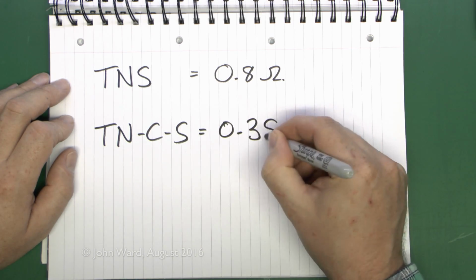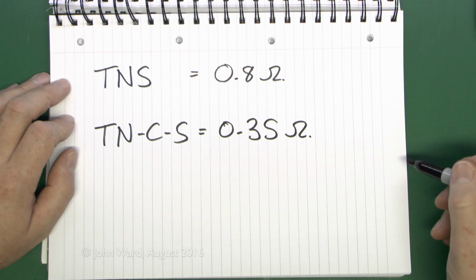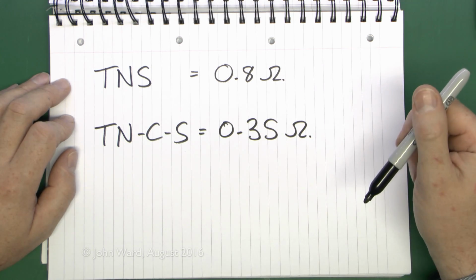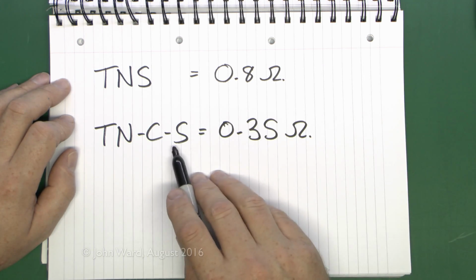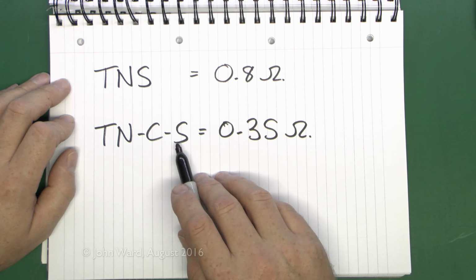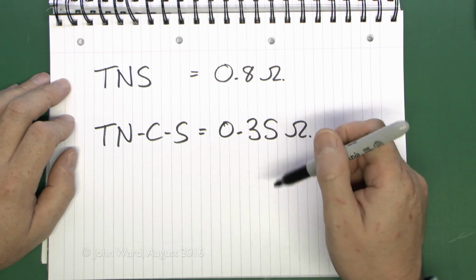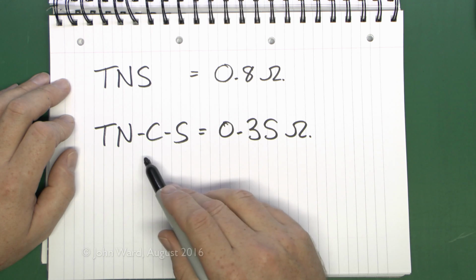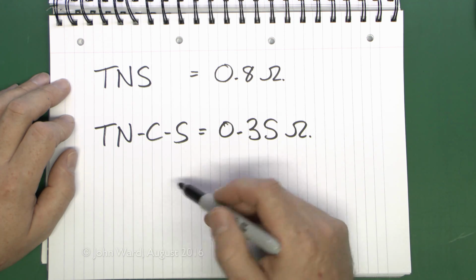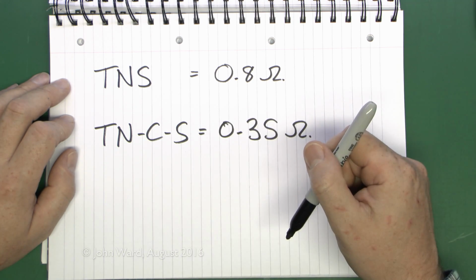For this type of system, a typical maximum is around 0.35 ohms, so quite a bit less than the TNS system. And on this one, you'll also find that if you measure between, say, line and neutral and line and earth, the value is generally the same, simply because it's the same piece of wire you're measuring. It's just that there are two terminals at the end. Of course, they're both connected to the same cable immediately as it leaves the building.